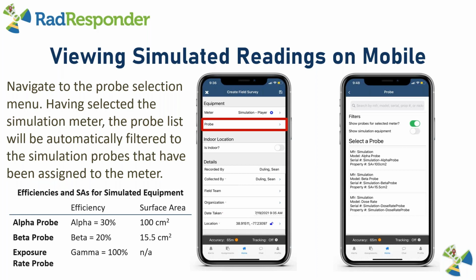You can see here it's quite simple. I've got an alpha probe, a beta probe, and a dose rate probe. Depending on what radiation type I'm measuring for, I'll make one of those selections. This table in the lower left shows the efficiencies and surface areas we're using for simulated equipment. The alpha probe has an alpha efficiency of 30% and a surface area of 100 centimeters squared. The beta probe has a beta efficiency of 20% and a surface area of 15.5 centimeters squared. And the dose rate probe has 100% gamma efficiency. Surface area does not apply.